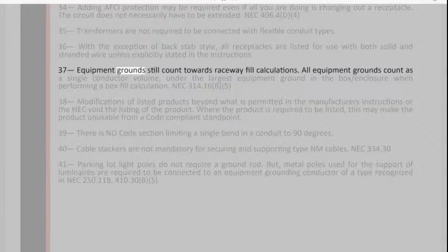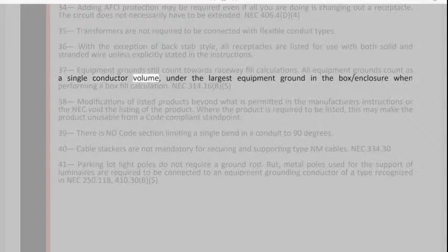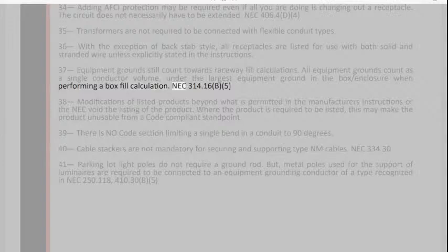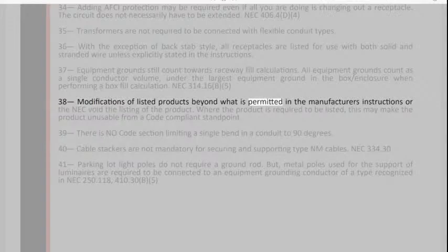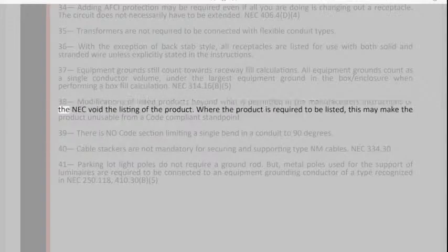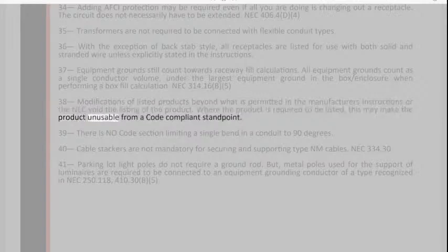37. Equipment grounds still count towards raceway fill calculations. All equipment grounds count as a single conductor volume, under the largest equipment ground in the box/enclosure when performing a box fill calculation. NEC 314.16, B5. 38. Modifications of listed products beyond what is permitted in the manufacturer's instructions or the NEC void the listing of the product. Where the product is required to be listed, this may make the product unusable from a code compliance standpoint.